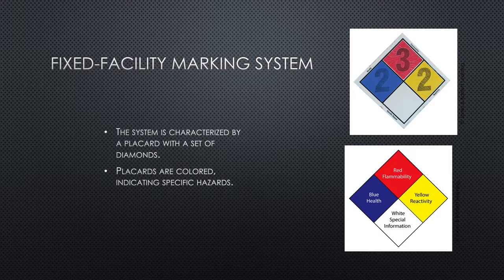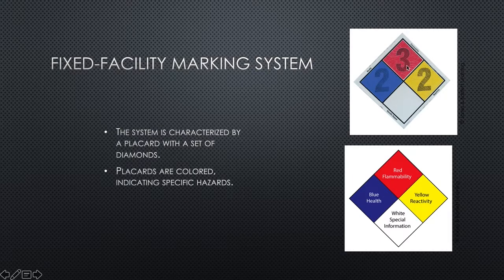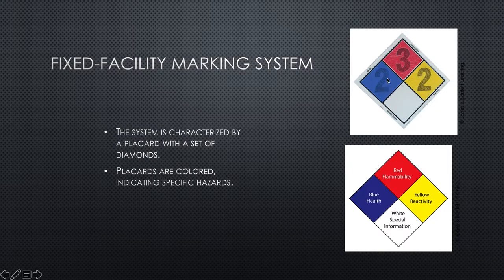The placards are color-coded, and each small diamond is rated on a scale of zero — no hazard — to four, which is severe risk. So if you were looking at a diamond and saw a three in the red, that's pretty risky for flammability, as it goes all the way up to four. A two would indicate moderate health risk and reactivity risk.